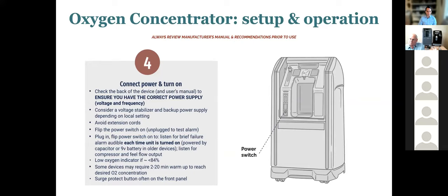Now, in some operating environments, which we'll go into in a little bit more detail in a minute, consider adding a voltage stabilizer or uninterruptible power supply, at a minimum, a surge protector in between the unit and the power that you're going to be using. Try not to use extension cords simply because of tripping hazard and also increasing the risk of failure in the circuit. If somebody requires continuous use of the oxygen concentrator, somebody tripping over it and disconnecting it obviously can cause some major problems.